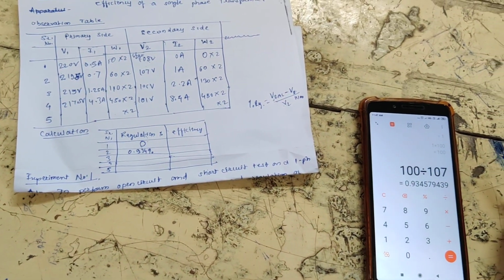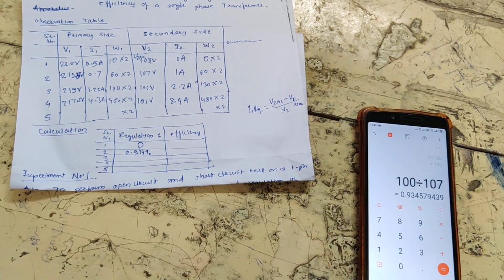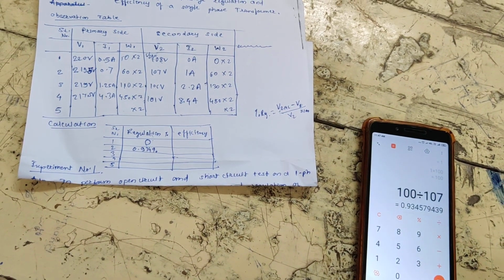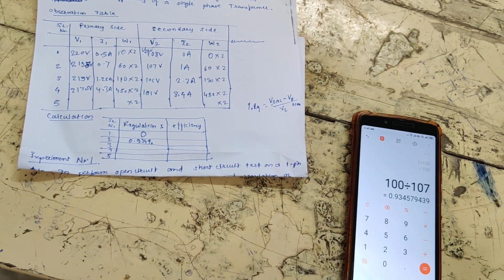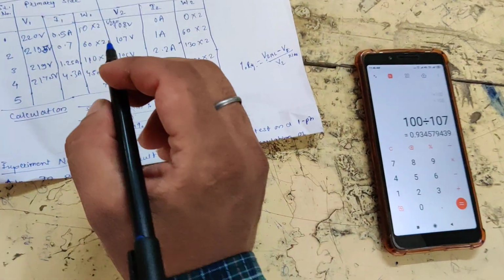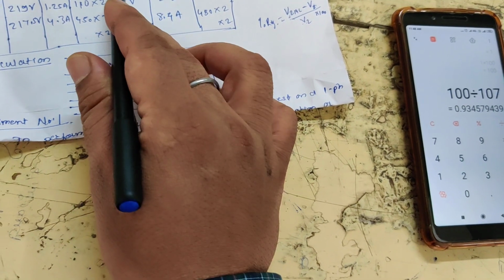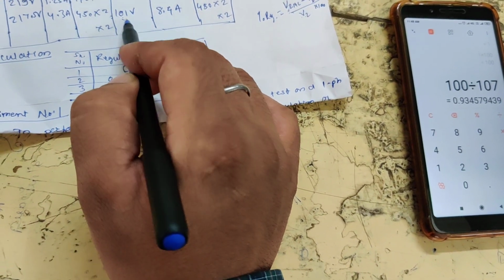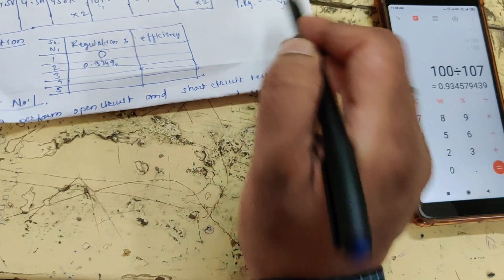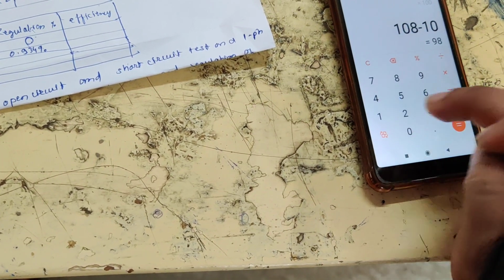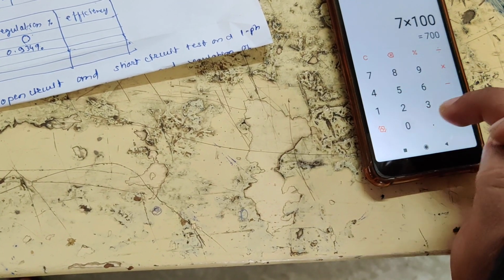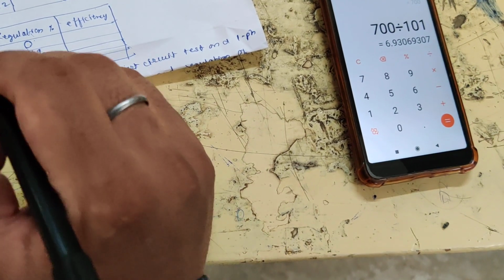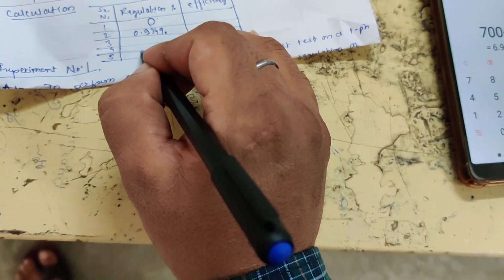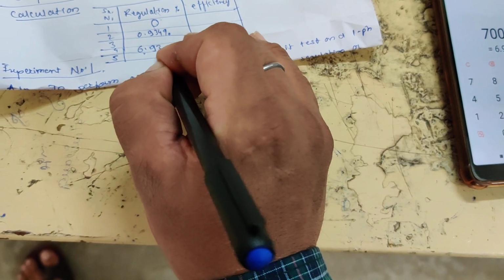So instead of multiplying by 100, if you are not multiplying by 100, it is in per unit. If you multiply by 100, it is the percentage. After that, talking about this reading, it is 108 minus 101 upon 101, that is V2NL minus V2 upon V2. So in this case 108 minus 101, multiply by 100, divided by 101, will become 6.93. So here the fourth reading is 6.93 percentage.